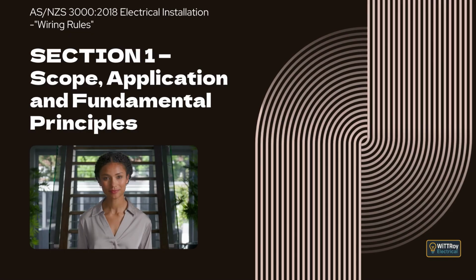Clause 1.5.11.2, Circuits operating at different voltages. This clause explains that protection must be provided to prevent injury or property damage if a fault occurs between live parts of circuits that operate at different voltages. Two methods may be used. The first method is segregation, keeping the circuits physically separated from each other so a fault cannot jump between them. The second method is installing devices that protect against overvoltage. These devices help limit or prevent dangerous voltages if a fault occurs between the circuits.